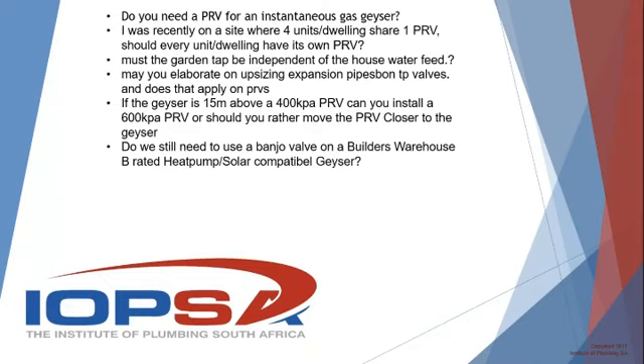Patrick summed it up quite nicely. You can't mix and match. That's quite clear: the PRV has to match the pressure rating of the geyser. You cannot mix and match that. You cannot MacGyver it to change it, because anything can happen down the line, and people subsequent to you can get confused.